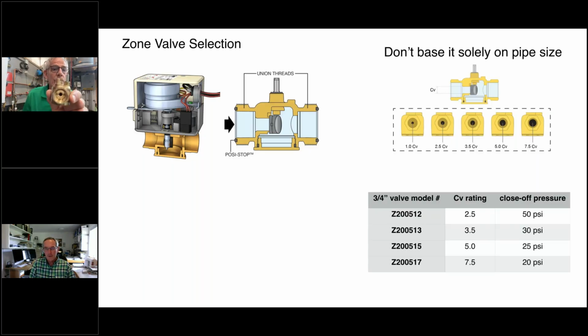Well, there's a zone valve with a 1 CV. It's a 3/4 inch zone valve, or actually it's a 1/2 inch, sorry, zone valve. And you can see the size of the orifice of the opening in that. And here's an example of a 7.5. So let's get them both side by side so you can see the difference there. So the question comes, well, why would I want a valve with such a tiny hole in it? And you can talk to why we make this valve and who would use that valve. Probably not a valve you're going to find at your wholesaler typically. That's going to be an OEM valve that a manufacturer specified that specific valve.